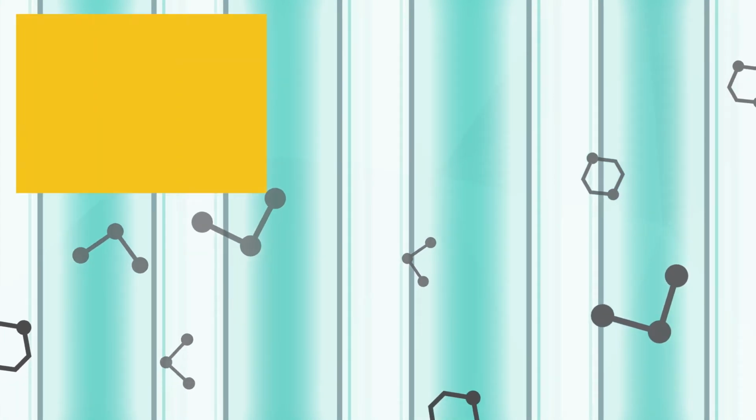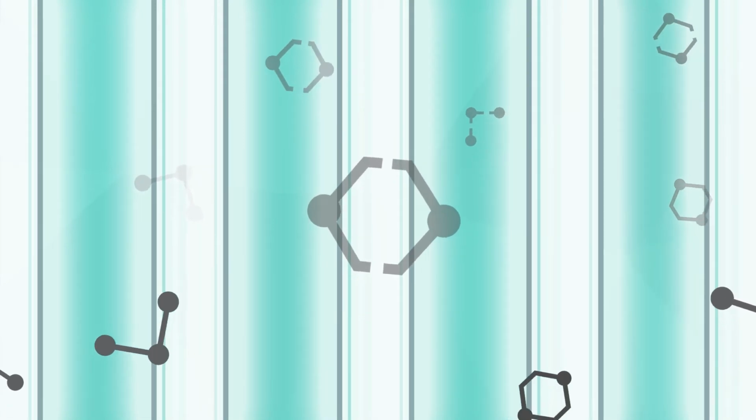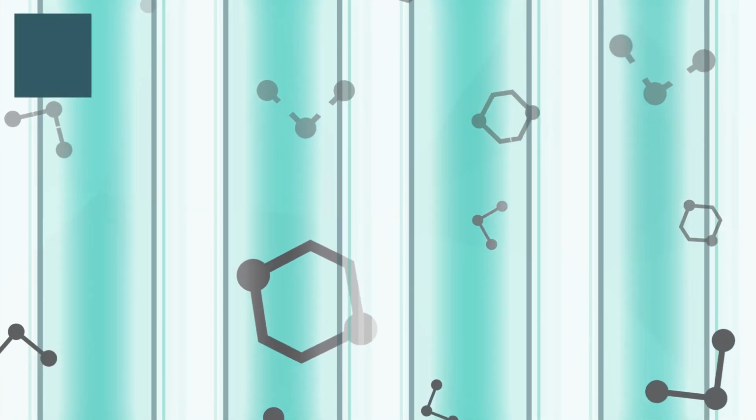As the biological and chemical contaminants pass through the UV chambers, they are exposed to and absorb the UV light emitted by the lamps. UV light is extremely powerful. Imagine your worst sunburn and multiply that by 1,000. Once the contaminants have absorbed enough UV light, their chemical bonds break apart. This reaction is called UV photolysis.